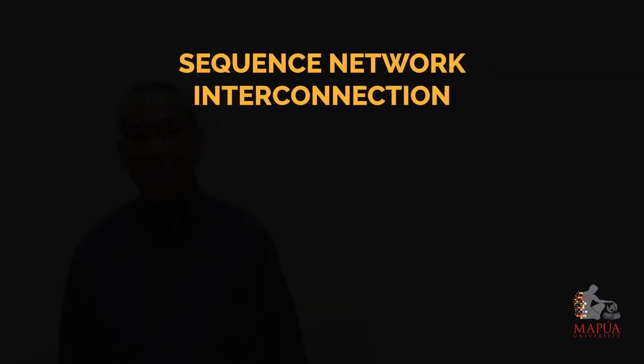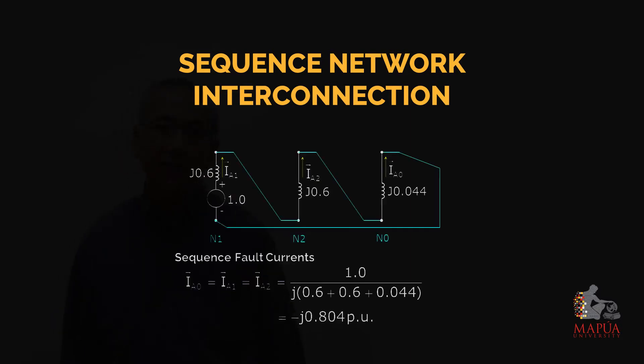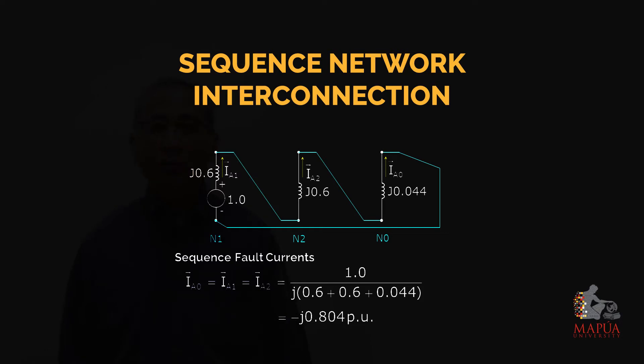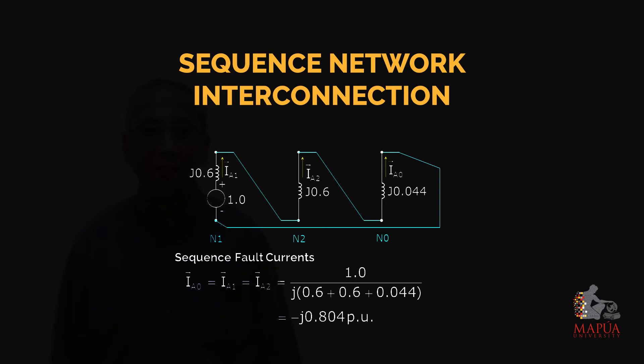Now for the interconnection of these three sequence networks for the single line to ground fault, the currents IA1, IA2, and IA0 are equal based on our computation, and the interconnection is in series. So IA0 = IA1 = IA2 = 1.0 divided by the sum of the sequence reactances: 0.6 + 0.6 + 0.044, giving a magnitude of -j0.804 per unit. These are the sequence fault currents flowing through the faulted point.